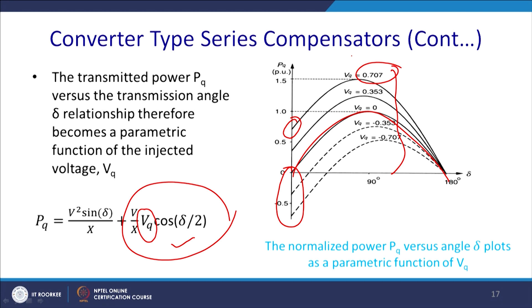So, straight away you get around 50% more power for 0.707 compensation, and also you can go in the negative direction. So, it has a huge power handling capability, minus 0.5 to almost minus 0.707 to 1.5. So, what we can conclude is the transmitted power PQ versus the transmission line angle delta relationship, and we have the following equation, and this will be the changed power dimension. What was initially just this value for VQ equal to 0 can ultimately go up and down with the help of this series compensation, and it is a very superior compensation compared to the change of impedance.